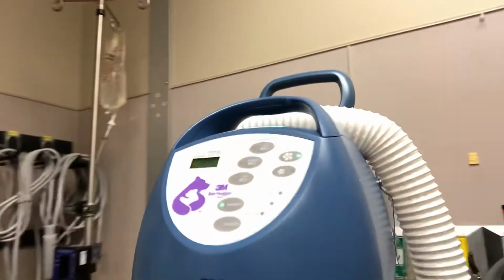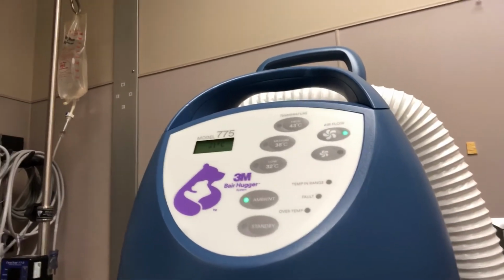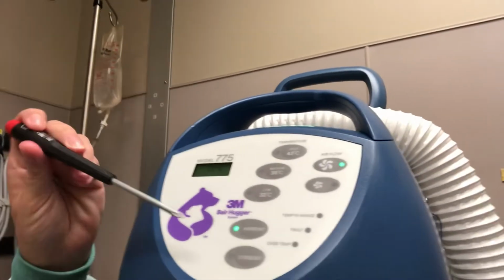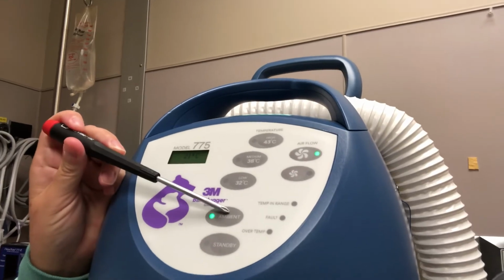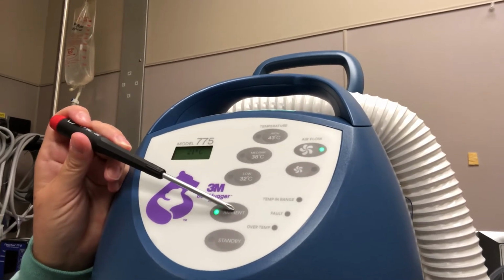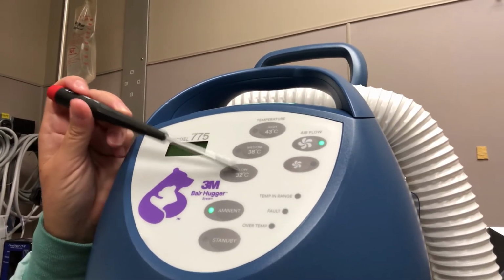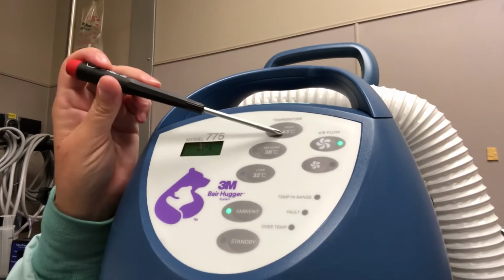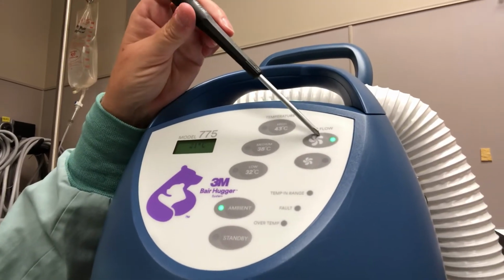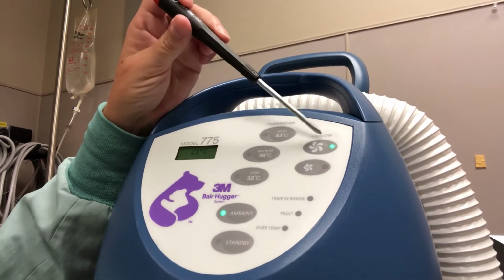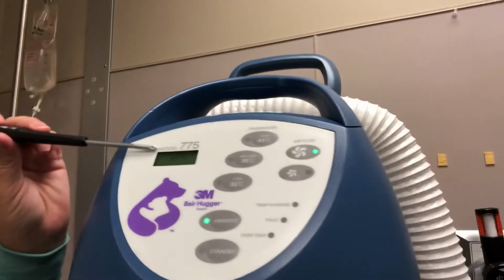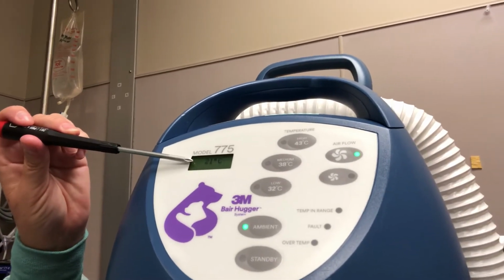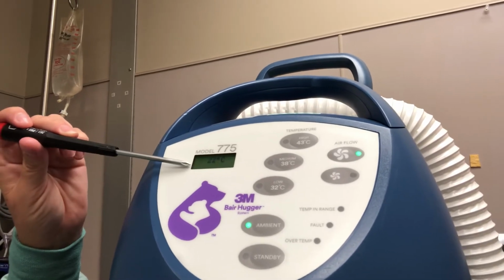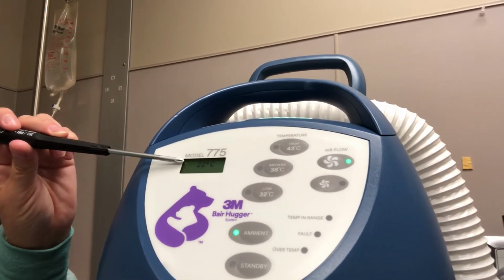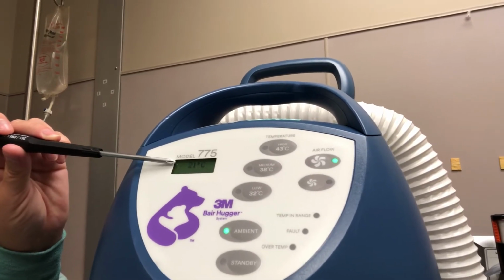I'm going to show you the front of this device a little bit closer. So here we have the standby button here, ambient temperature, which is lit up. That means that's what we have right now on. We have our 3 different operating temperatures, 32, 38, and 43 degrees Celsius. We can choose high flow or low flow. For all testing, we want high flow. And then our display shows us our actual, or what the unit is reading for the temperature. So right now it's reading between 21 and 22 degrees Celsius.